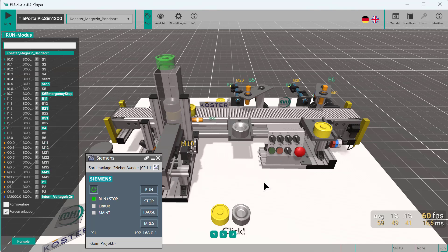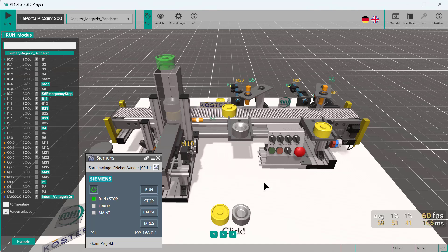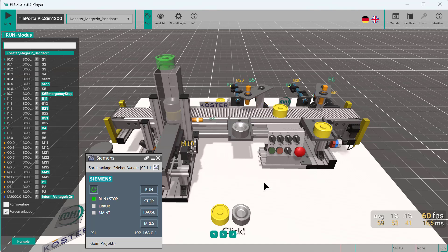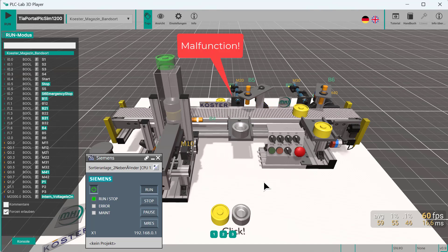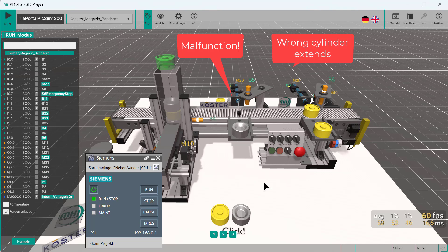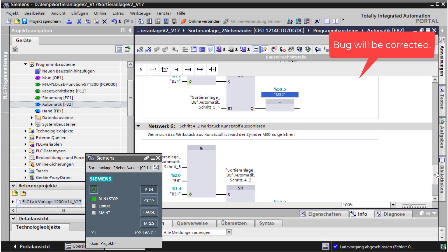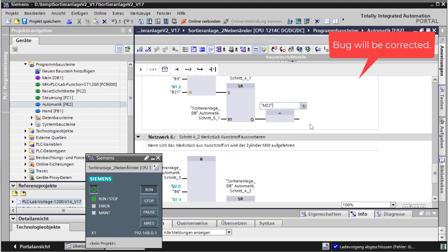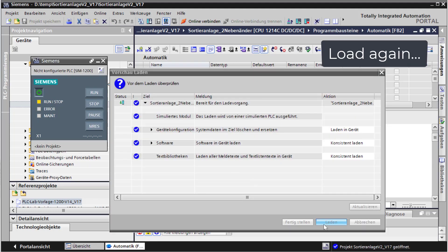If the program has been programmed correctly, the 3D model will move and react as expected. If this is not the case, troubleshooting follows with the help of the tags window and the watch function in the TIA portal. Sometimes the error is obvious, making it easy to quickly locate and fix it. Fix the error in the control program, translate it and transfer it back to the PLC SIM.